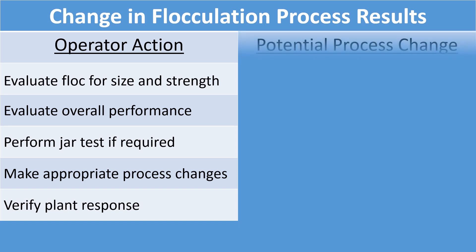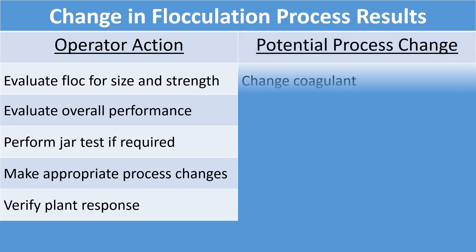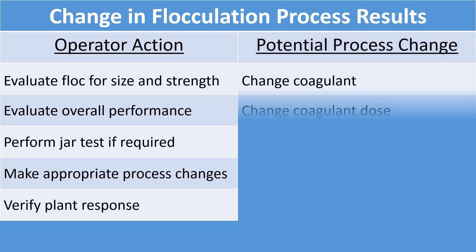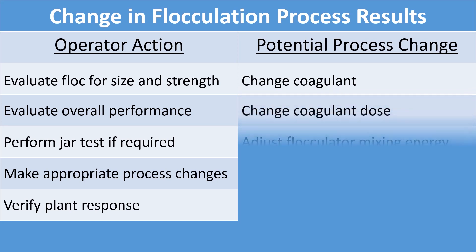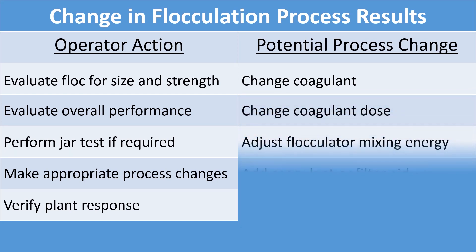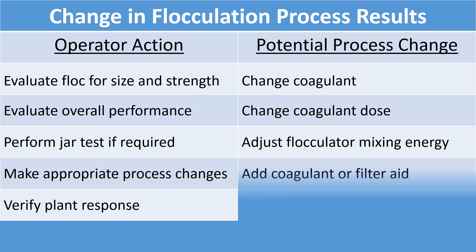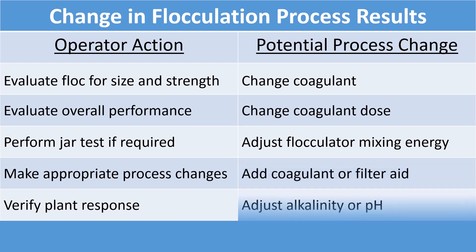The potential process changes that the operator can make include: changing the coagulant, changing the coagulant dose, adjusting the flocculator mixing intensity, adding a coagulant or filter aid, and adjusting alkalinity or pH.